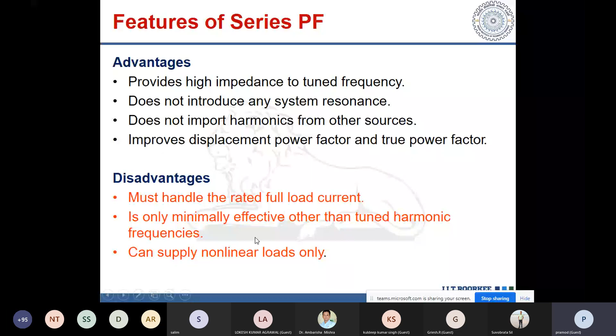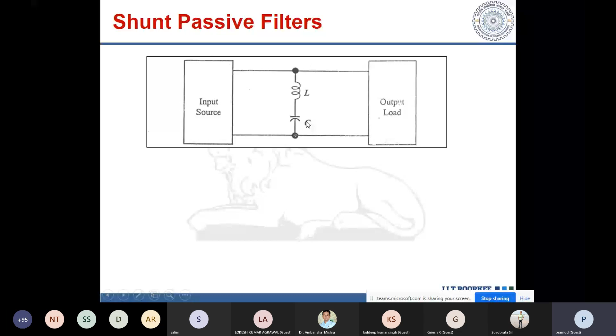Then you have the shunt passive filter, which is a parallel filter, but it is a series LC tuned filter, a series combination of L and C. It is a very popular method to control the propagation of harmonics. Since it is tuned to a particular frequency, if the load injects current at that frequency, it will be absorbed by this filter, and that current will not travel to the line and the rest of the system. In that way it prevents the propagation of harmonics. It is also referred to as a sink because it absorbs the harmonic current.